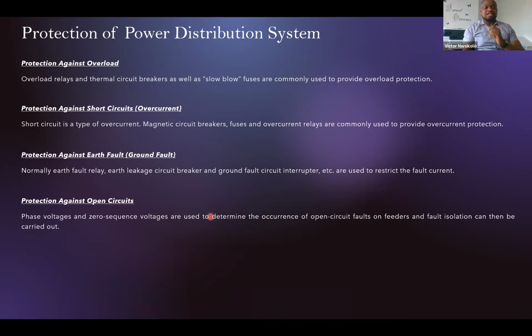Then we also have protection against open circuit. Open circuit doesn't have a defined protection, but it can be monitored in a controlled distribution system where we have sensors or detection equipment in the line that measure the balanced three-phase. If for any reason we have a drop of one phase, it picks up a zero sequence voltage and sends that information to the system. In some cases, those systems are further automated to cut off the supply. Open circuit is considered a fault because in a distribution system with three-phase supplies, if we lose one of the phases, a section of the consumers will lose power. So you want to monitor that.